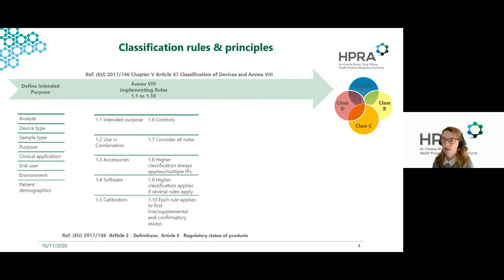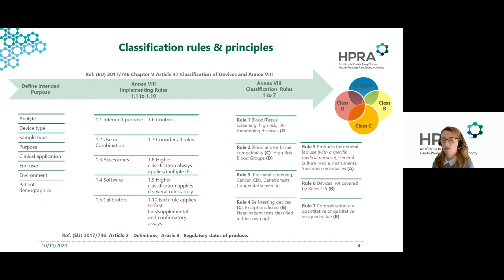So then there are 10 implementing rules as per Annex 8 of the IVDR, and then there are 7 risk-based rules. This risk-based system is very important to ensure that the level of regulatory oversight is proportionate to the risk of the device.